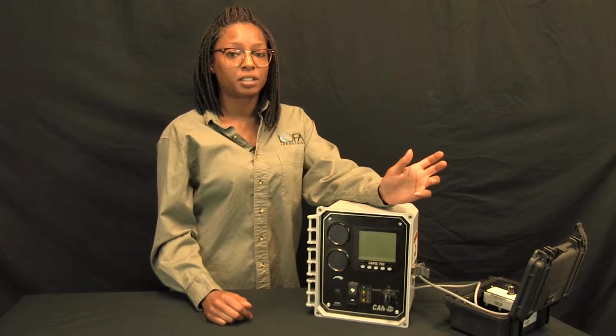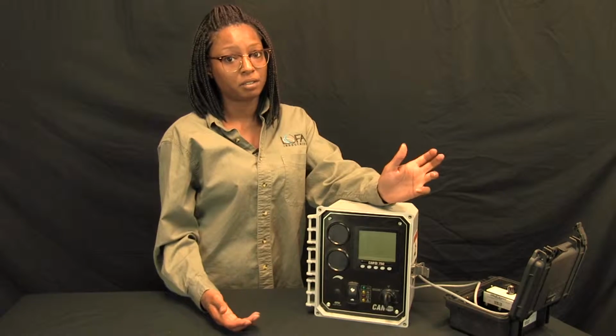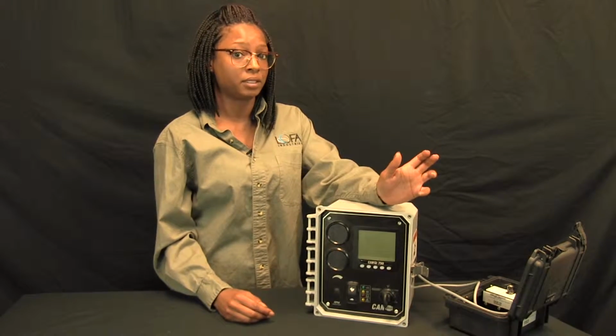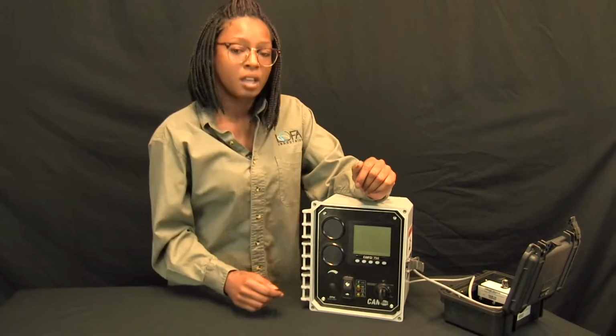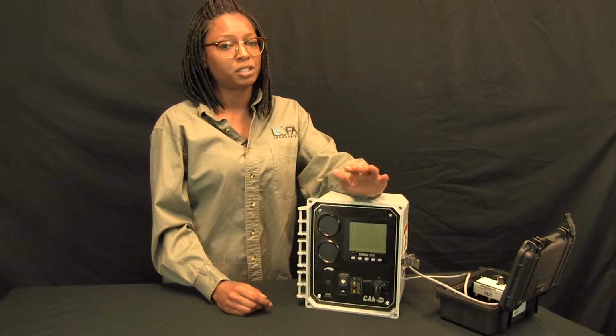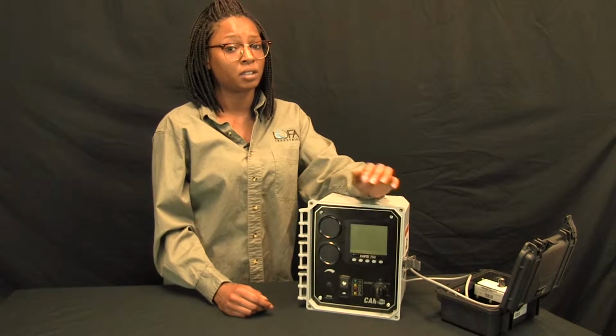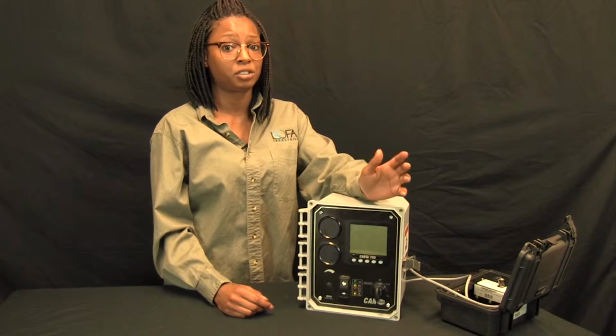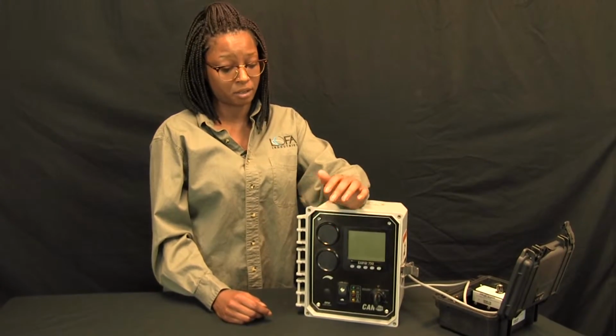So in order to get into the AutoStart parameters, you have to turn the key to the run position and hold down the far right button to get into the configuration menu. Just be mindful that you don't want to change any of the parameters for the CP750 in AutoStart mode due to the fact that the engine might start if a start event is current.